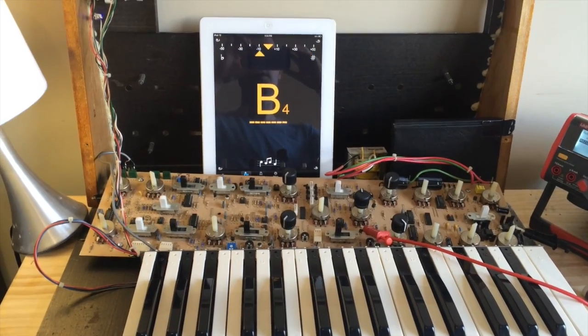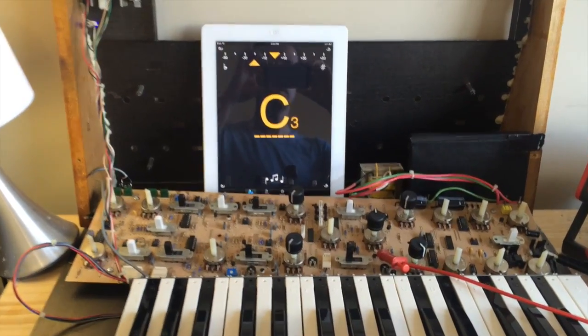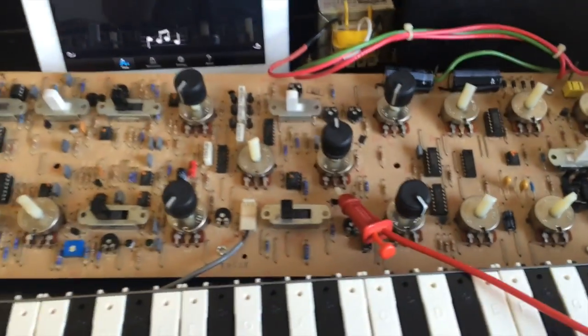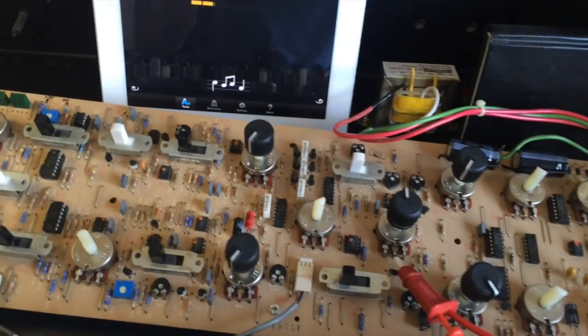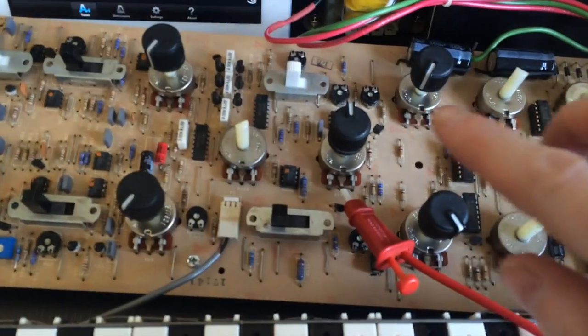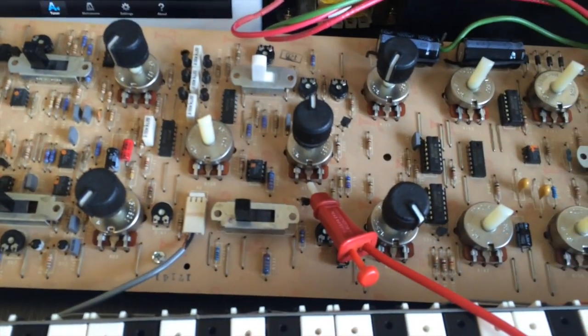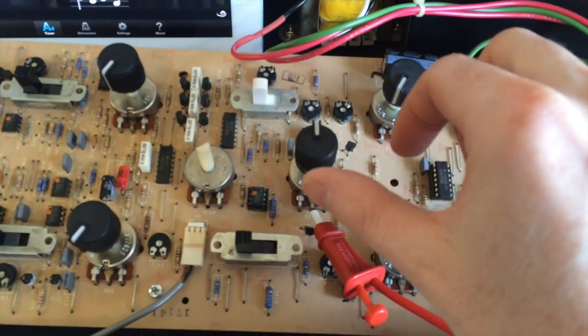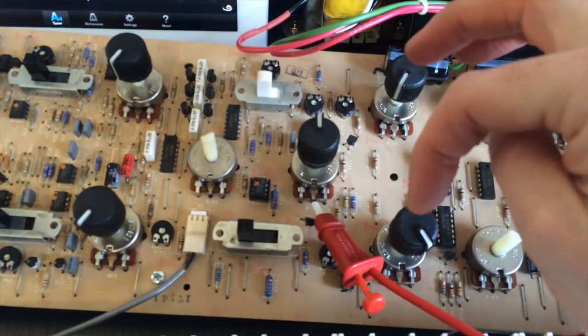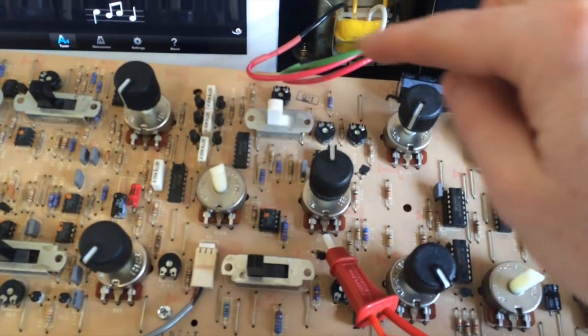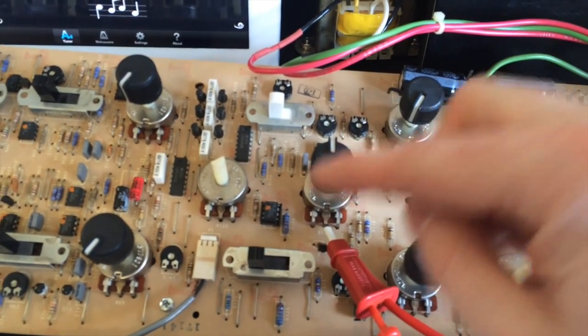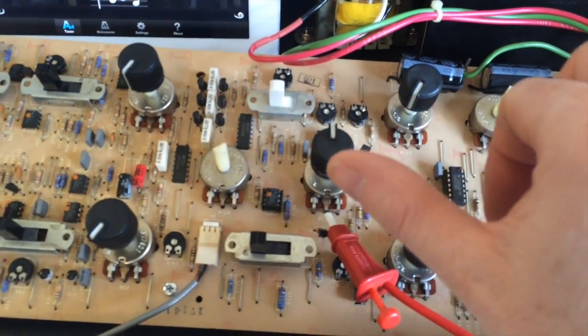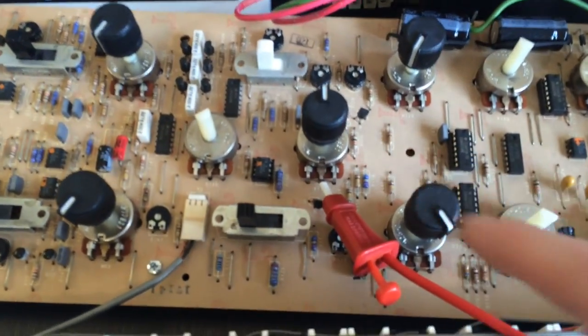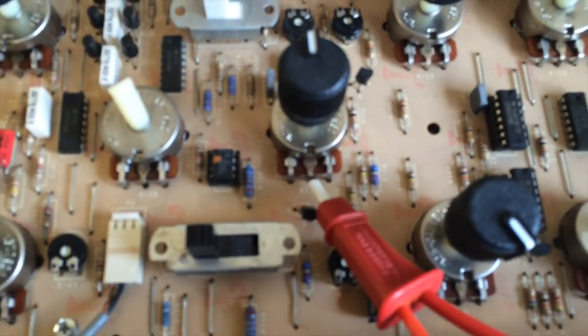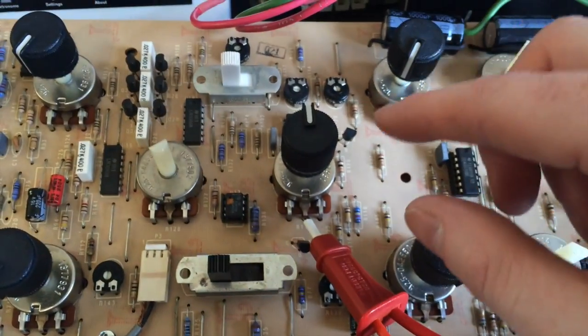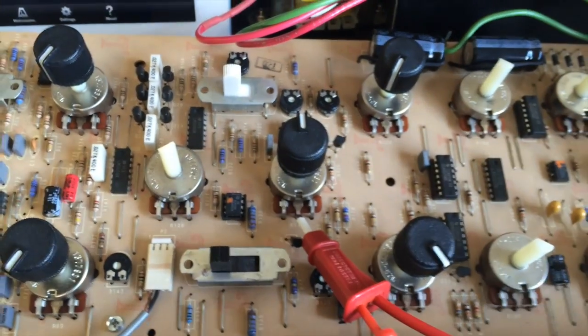Okay, so we're up to the filter calibration. The first part, the manual's not very clear. It says to set the filter frequency to 0. That doesn't mean you turn the pot all the way to 0 like the scale is written on the front panel where you've got 0 and 10. It means electrical 0. So if you try and do it the other way with the pot all the way around, you won't be able to calibrate.